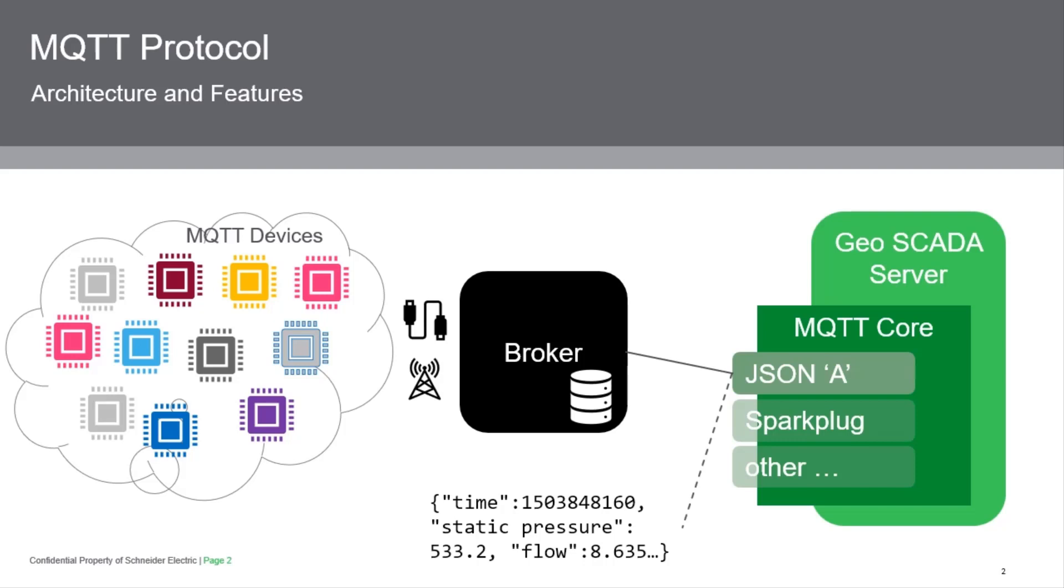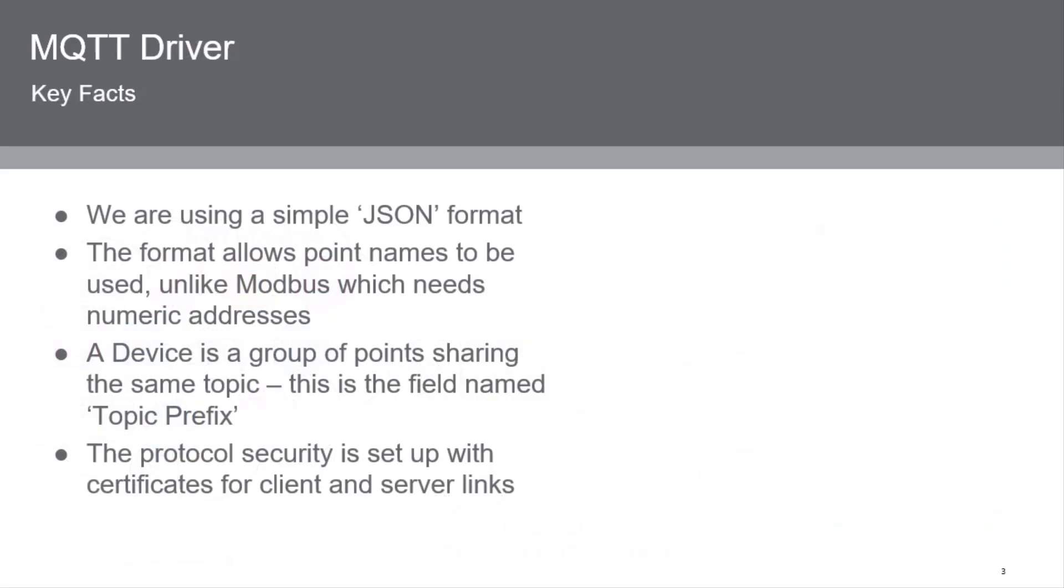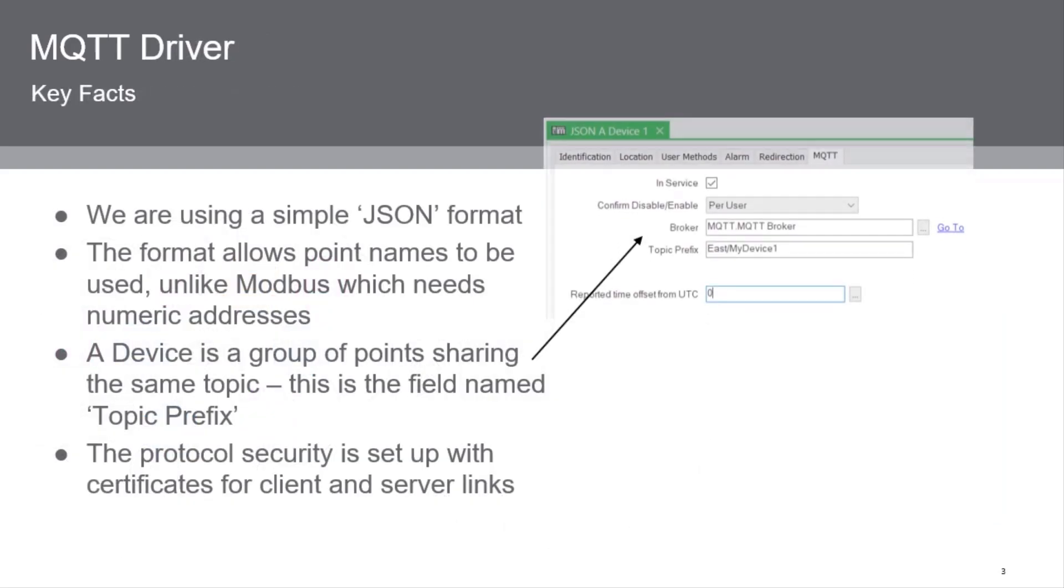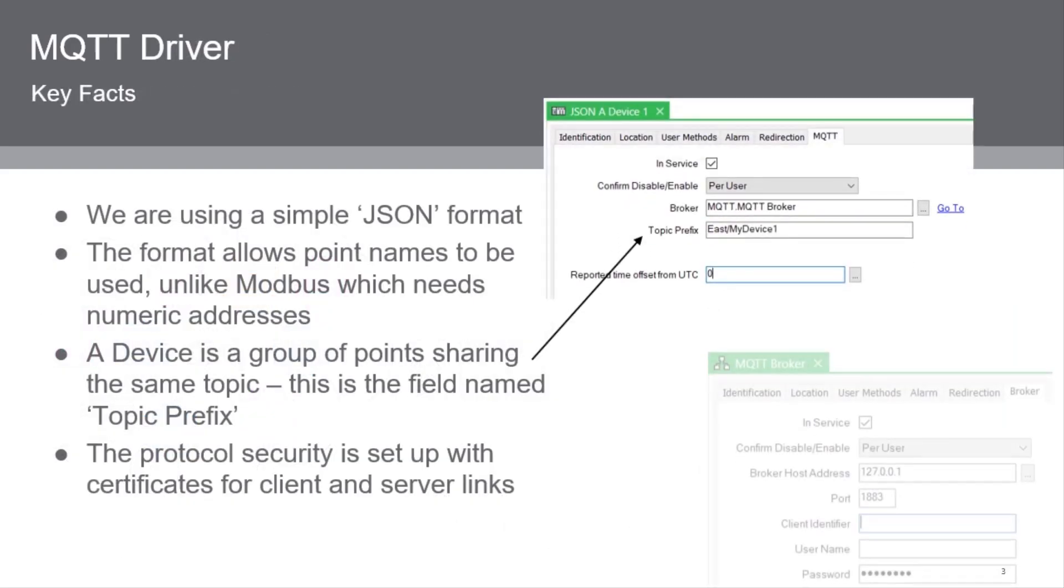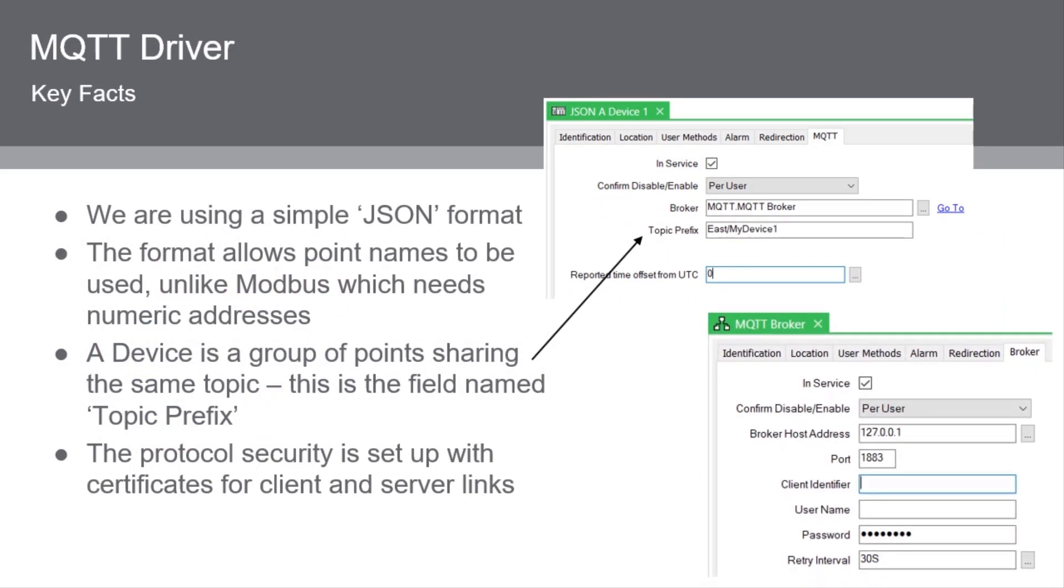In future, we'll add more protocol content, such as Sparkplug B. The format allows point names to be used, unlike, for example, Modbus, which needs numeric addresses. The point name is specified in the JSON message. A device is a group of points sharing the same topic, and this is the field named Topic Prefix. The topic is what addresses the data in MQTT. The protocol security is set up optionally with certificates for client and server links.